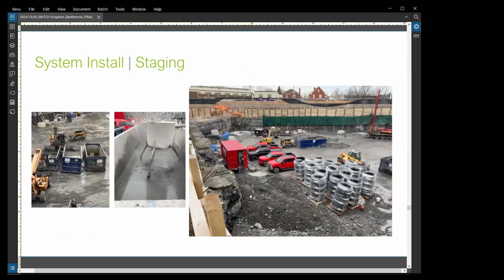Once the rock is out and the excavation is in, this is where we got the booms in. These coils here are essentially the pipe, which comes pre-measured — you tell the supplier you need 600 foot lengths, 800 foot lengths, and it arrives with a pre-molded turn at the bottom, so they're not bending pipes or creating that turn on site. They just feed the bottom part into the pipe, and because it's all pre-measured and placed at the set location, it sticks out exactly where it needs to be.